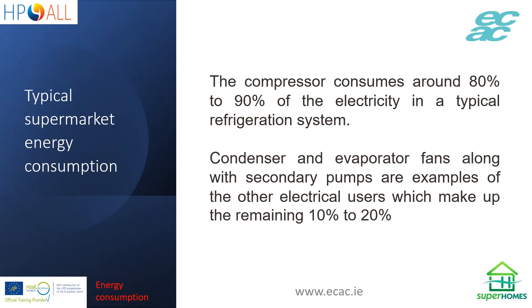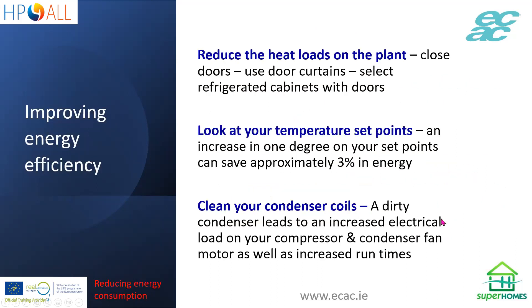The compressor consumes about 80 to 90% of the electricity in a typical system. The condenser and evaporator fans, along with any pumps and the control system, make up the remaining 10 to 20%. To improve energy efficiency, the obvious step is to reduce the heat load on the plant — that means closing doors and using door curtains on refrigerated cabinets. Look at your set points: if you can increase the set point by one degree, you can save approximately 3% energy. If you don't have to go down to two degrees and could survive at four degrees, there's a potential 6% energy saving.